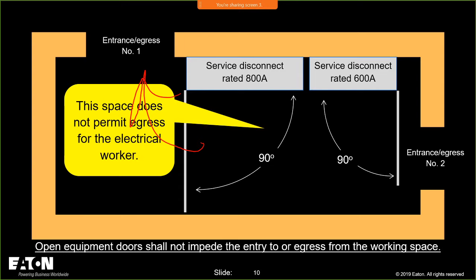Another possible angle, though the code doesn't quite address it, is removable doors for when you're doing work. You'd have to talk to your AHJ, because the language just says open equipment doors shall not impede entry to or egress from the working space, not doors that have been removed. I'm not an AHJ, so I can't say what's good or bad, but I think this will have a huge impact on a lot of designs.